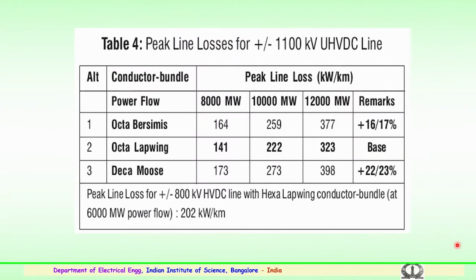So, if it is used, then how are the line losses, the conductor bundle for various configurations, the power flow? Using the 8 conductor Bersimis conductor, what will be the peak line loss, estimated in kilowatt per kilometer? If the 1100 kV UHVDC line is used with 8 conductor Bersimis and carries a power of 8000 megawatts, what will be the loss? 164 kilowatt per kilometer. In case of 8 conductor lapwing the loss will be 141, and in case of 10 conductor Moose the loss will be 173 kilowatt per kilometer. This is for a transfer capability of 8000 megawatts.